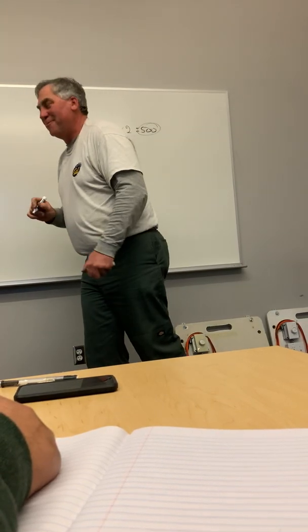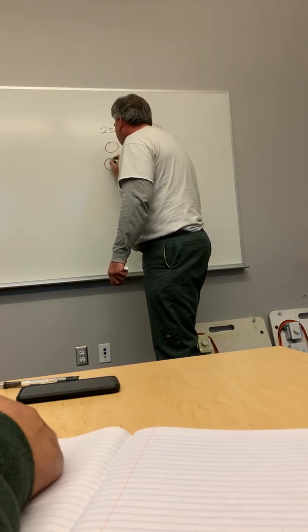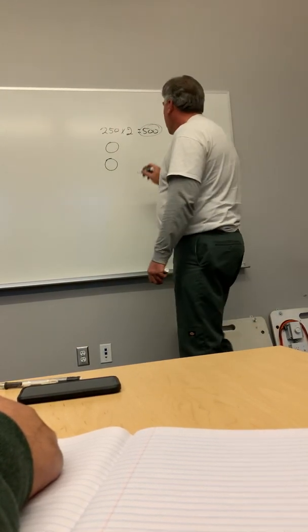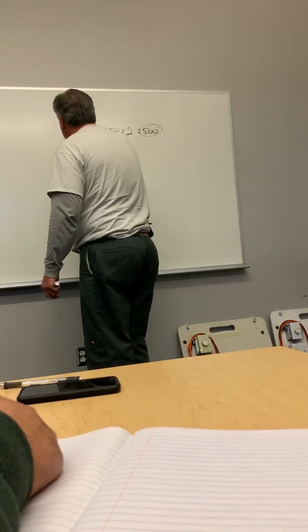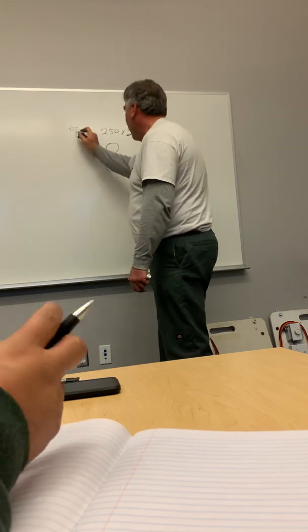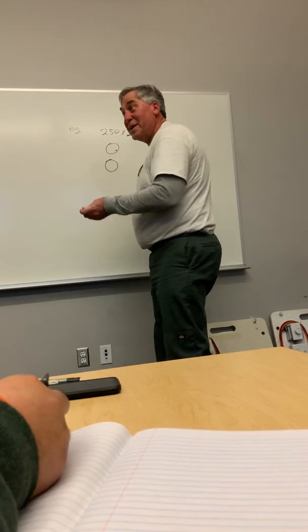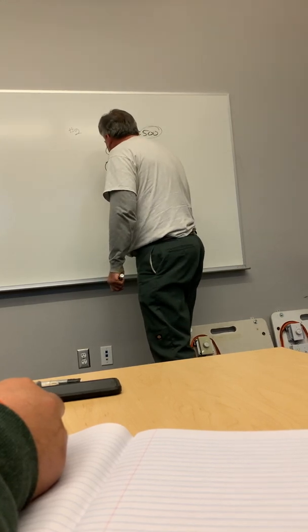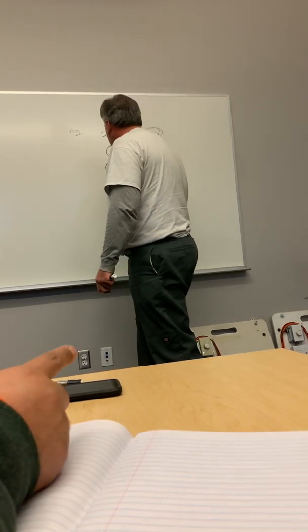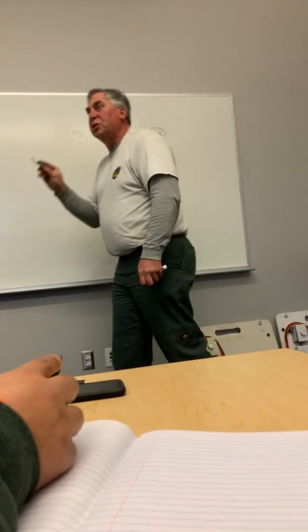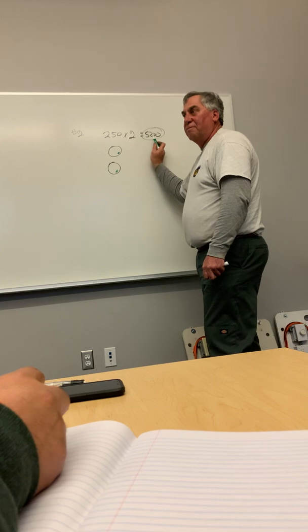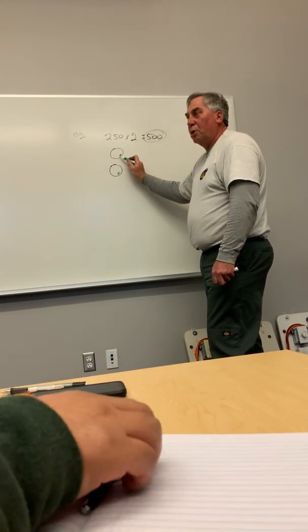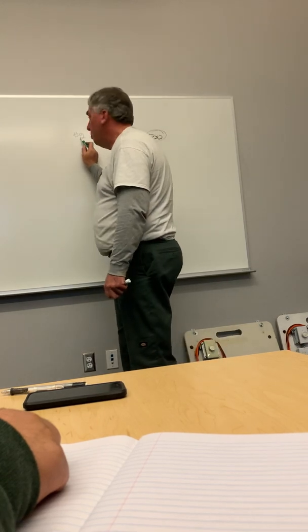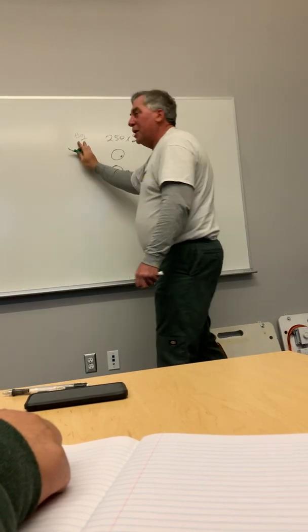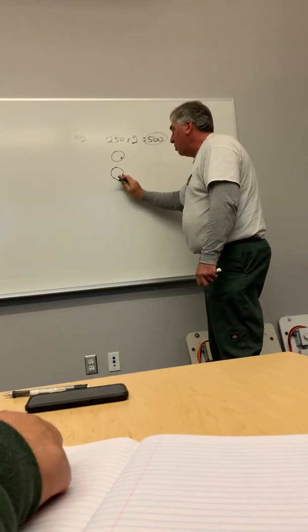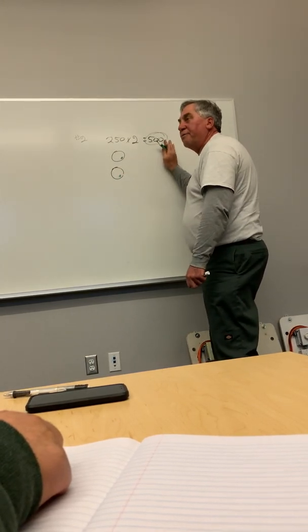But now here's the tricky part. It's in 2 different raceways. You cannot divide that number 2 and split it into 2. I gotta have my green pen. You have to have that number 2 in each one of these, because either one of those grounds has to be able to carry the full ampacity if the fault is imposed on this one or this one. If you were to cut it to, I don't think a number 1 is half, but then if there was a fault current in this pipe, it wouldn't be enough, right?